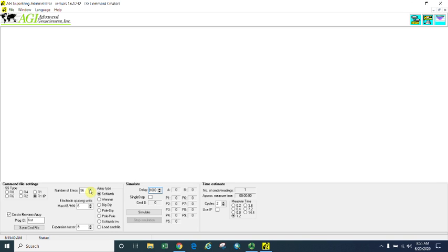This is working exactly the same as the soil resistivity test, except now we have 56 electrodes over a long spread, with spacing anywhere from a meter all the way up to 5 meters, so quite a bit of cable to deal with. And of course, it's going to hook up the probes or cycle through the probe configurations automatically. And you'll see what that looks like in the simulation here.